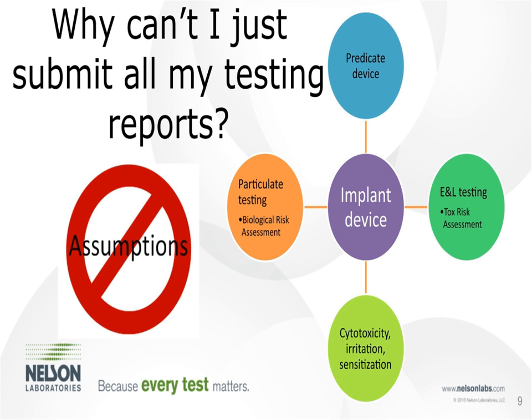Many people have simply submitted their testing reports in the past. But just submitting testing reports leaves a lot of room for assumptions, and reviewers will not make those assumptions. What they want to see in a BER is your scientific reasoning for why your device is safe — those connections need to be made.